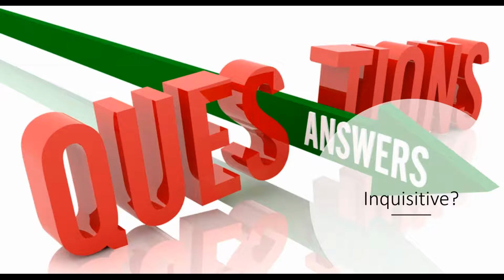Got it. The next question is, what should be the ideal noise level for a quote unquote good transformer? Now, I'll guide you to another guideline for the transformer, which is NEMA TR1. The NEMA TR1 guideline gives you the exact sound level, or the limit of the sound level, based on the size and the kVA rating of the transformer. The definition of good transformer noise is based on how you hear the transformer. So I would go with the NEMA TR1 rating on that particular aspect. So NEMA TR1 is the baseline.